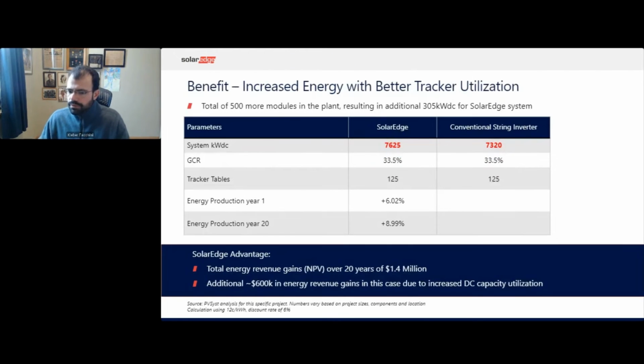So what this means is that by allowing the developer to fully use the tracker table, the developer can place 4 more modules per tracker table, and the net effect of this is that there are 500 more modules in the plant for the SolarEdge system, which totals 305 kilowatts DC more DC power, using the same number of tracker tables and the same GCR.